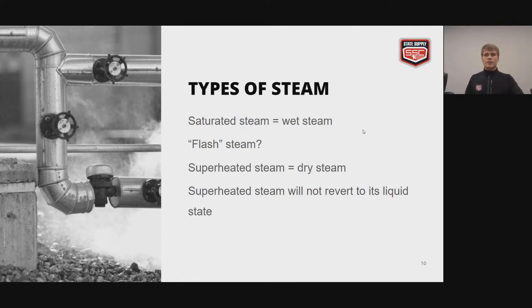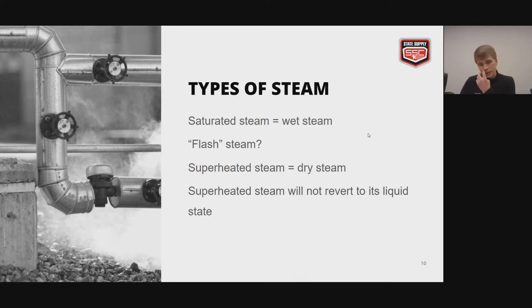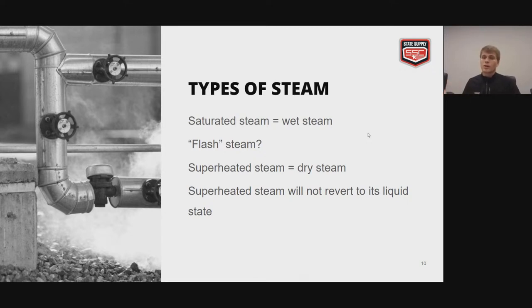Let's go over the types of steam. The first type is saturated steam, which means the steam is at the boiling temperature of water for that pressure — in open air, that's 212 degrees. Steam and water will both exist at 212 degrees under the right conditions, making it a wet steam. Whenever that steam loses its heat, water droplets will begin to form. Water can accumulate, and if you're using an uninsulated pipe, enough water could build up and create water hammer.